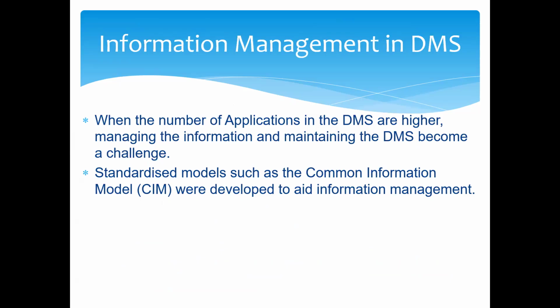Then we are going to talk about information management methods in the distribution management system. When the number of applications in a distribution management system is higher, managing the information and maintaining the DMS become a challenge. For example, in North Central Province, we had transformers close to 3,000. If we get the information about transformer power import, power export, current in three phases, voltages in three phases, and power factor, there are many inputs, multiplied by 3,000. So it's not easy, because a lot of data is coming from the network.